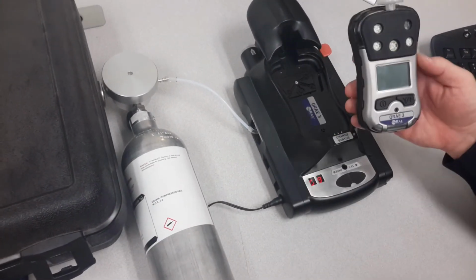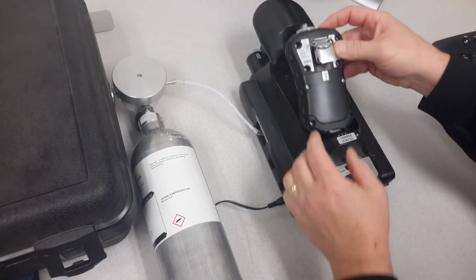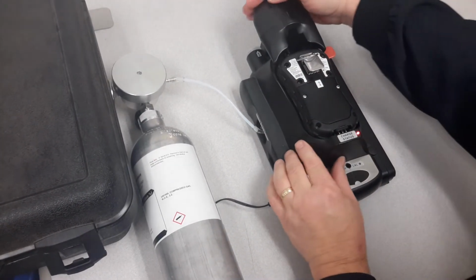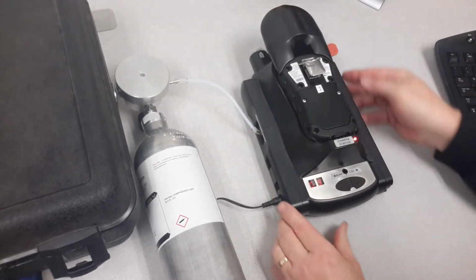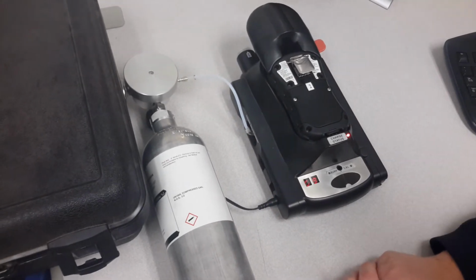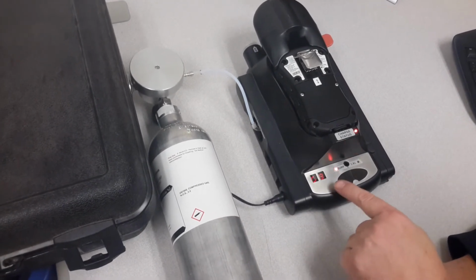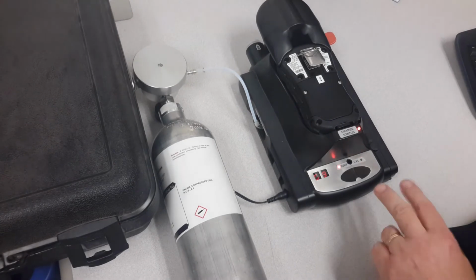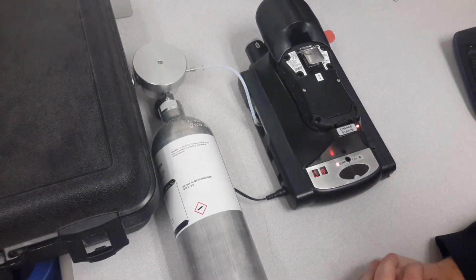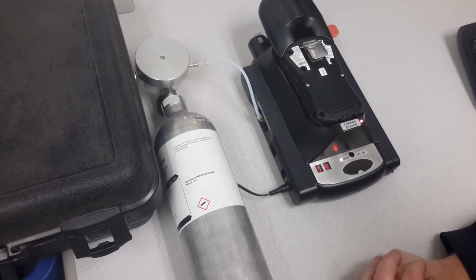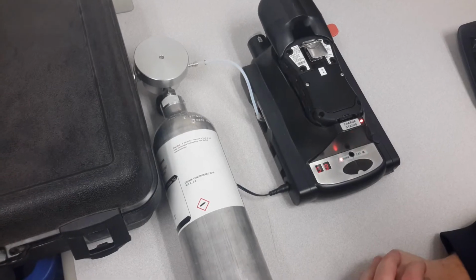And with the meter, it doesn't have to be on. Just go ahead and turn it upside down, set it in here, put it down, and the meter will automatically turn on, and you'll see the indicators will bounce back and forth. They'll do that until the meter is set up and ready for calibration.